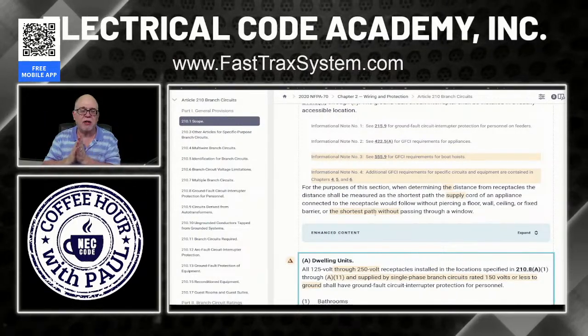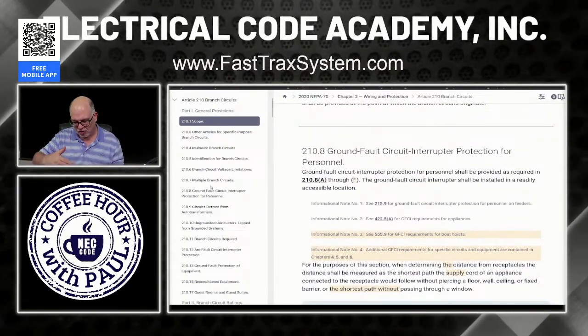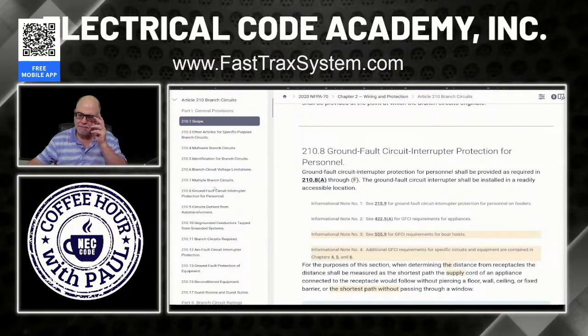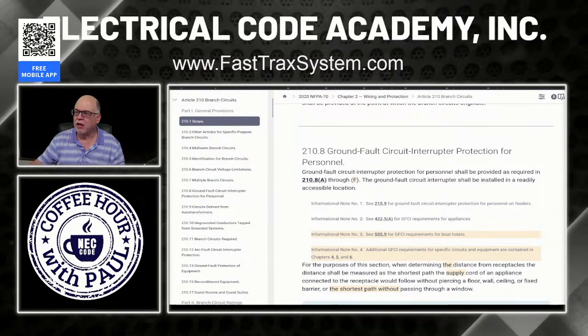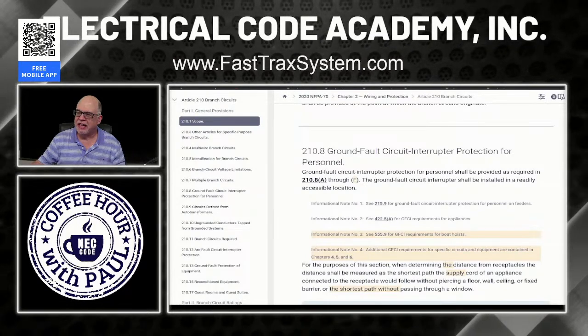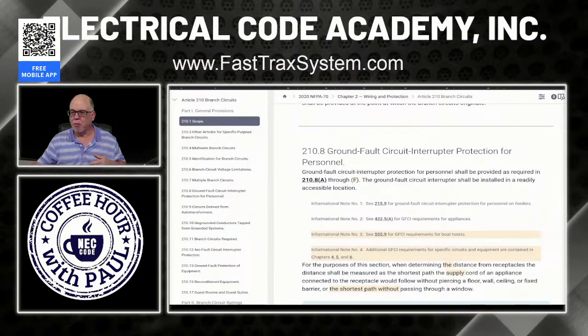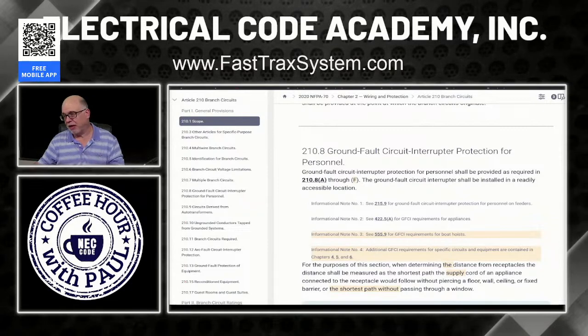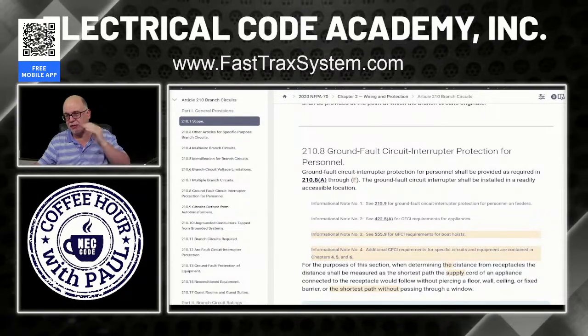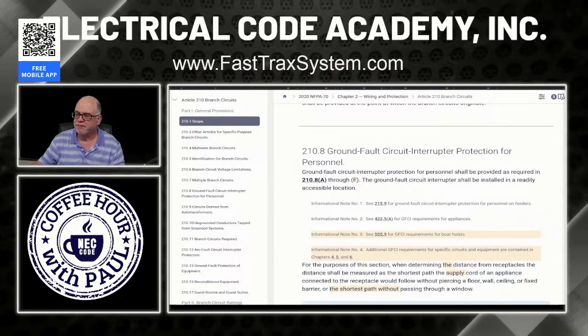So this would require GFCI protection regardless, because I guarantee you, if you look under the sink and you measure from the edge of the sink, top inside edge, those receptacles are going to be within 6 feet, okay? And of course, E says receptacles located inside the cabinet cupboard do not count as the required kitchen countertop receptacle. Well, obviously not, okay? Because they're more than 12 inches below. They're in the cabinet, by the way, and they're not in the countertop, and they're not within 20 inches of the top of the countertop. So obviously they would not serve the spacing requirement, okay? That just goes without saying.